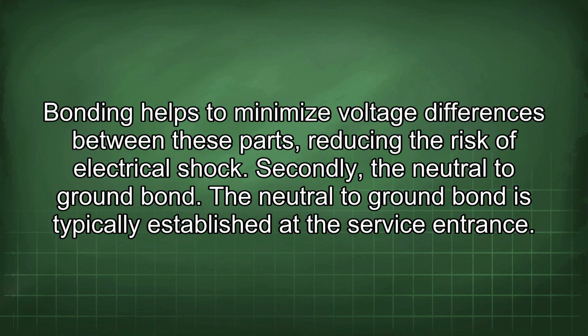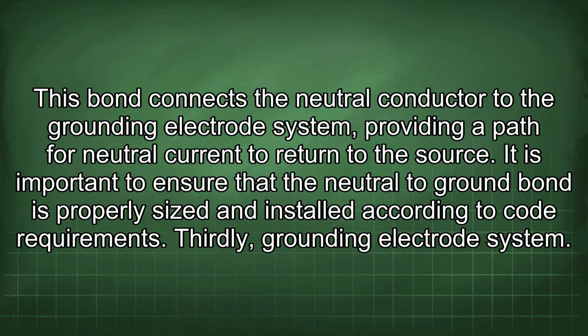Secondly, the neutral to ground bond. The neutral to ground bond is typically established at the service entrance. This bond connects the neutral conductor to the grounding electrode system, providing a path for neutral current to return to the source. It is important to ensure that the neutral to ground bond is properly sized and installed according to code requirements. Thirdly, grounding electrode system.